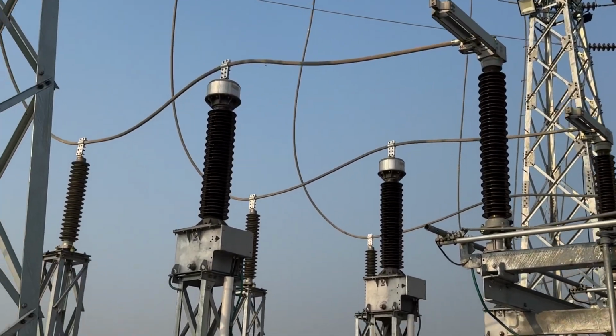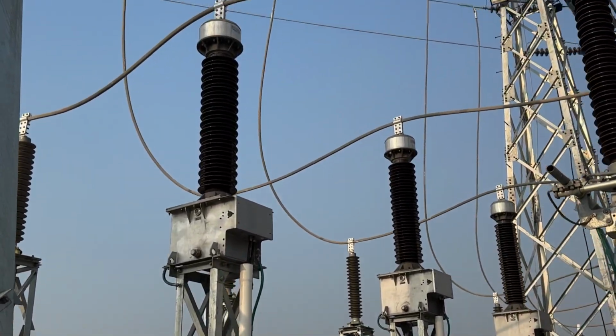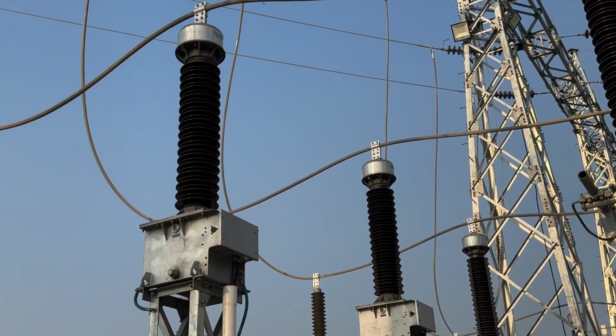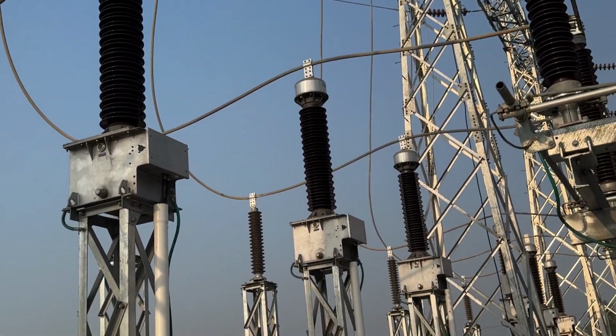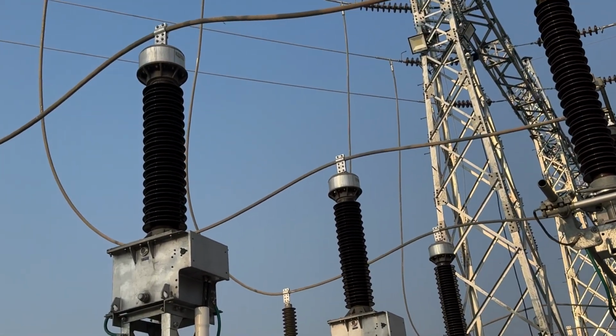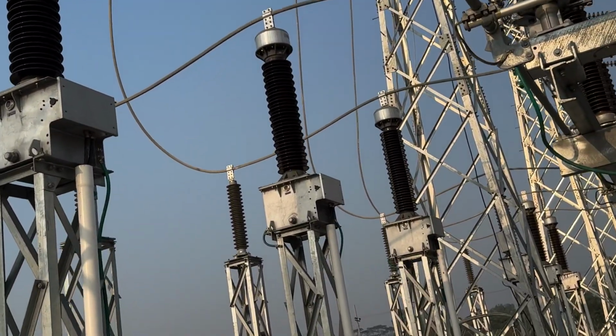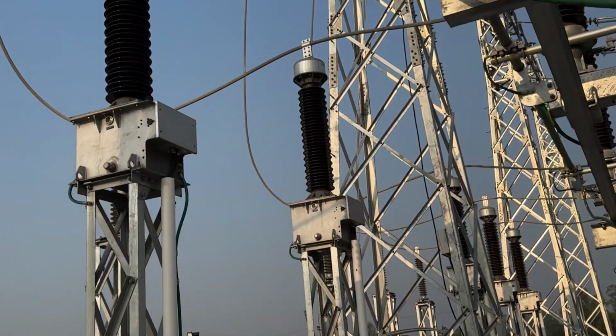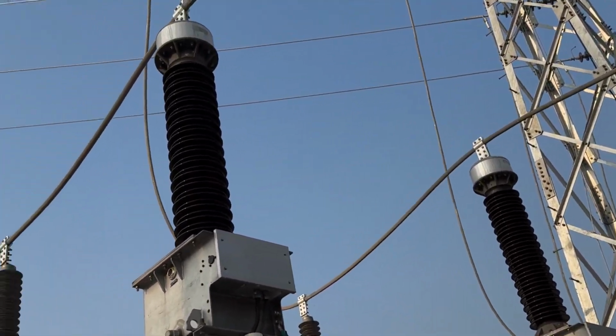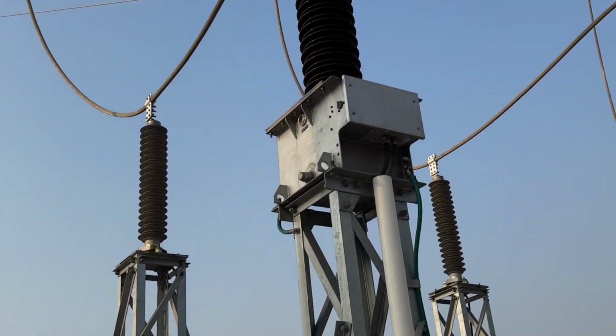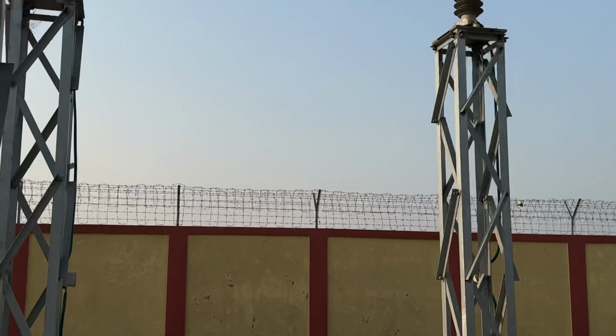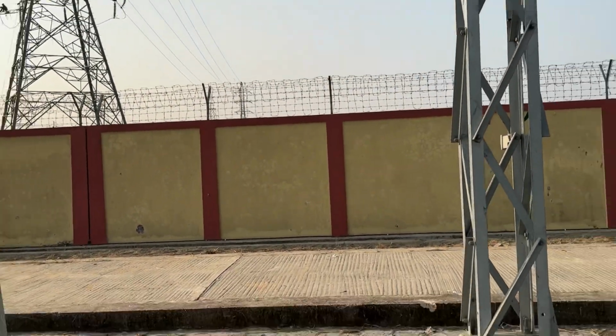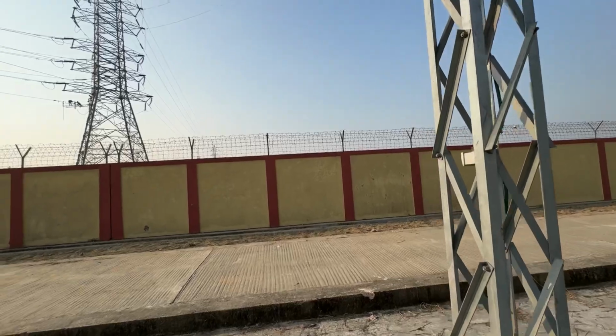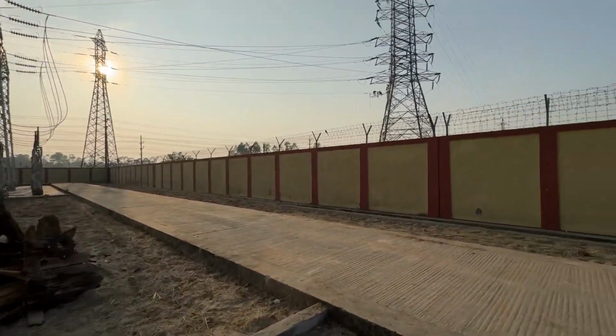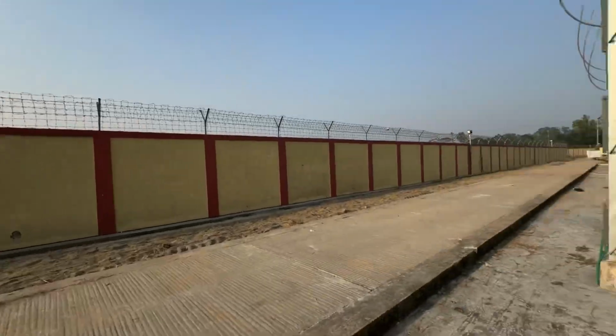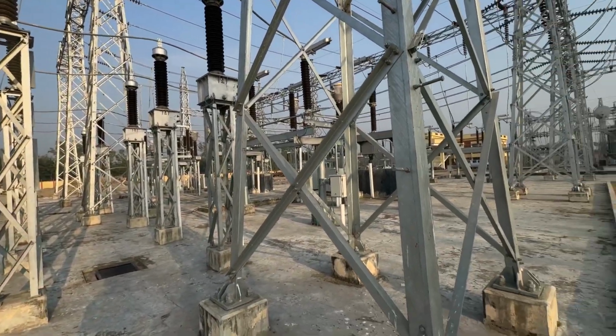After the isolator, there is a potential CVT, capacitive voltage transformer, a set of capacitive voltage transformers. There are also 3 capacitive voltage transformers. What is inside a capacitive voltage transformer? Normally, the construction of a potential transformer. What is the function of a potential transformer?